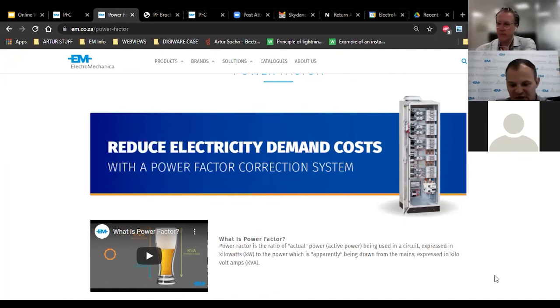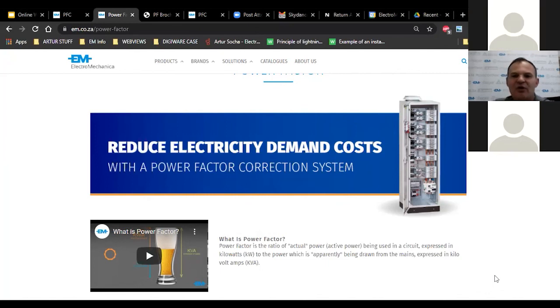It really depends on your site. So you'd have to first do some basic logging to determine what is worse. Because if you've got really bad harmonics, a normal power factor system is not going to work for you. Then you're going to have to look at the harmonic side of it. But I can use an example. I had a customer with a basic crusher, conveyor belts, not even soft starters, just star deltas. In his scenario, the most economic, best money spent was just capacitor banks. But he didn't have harmonics. And he reduced stress on his transformer.